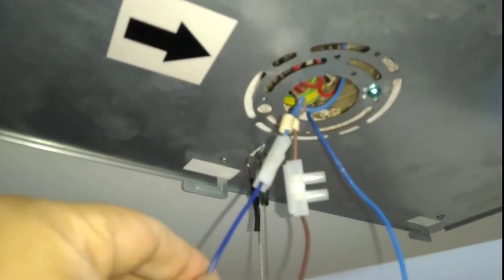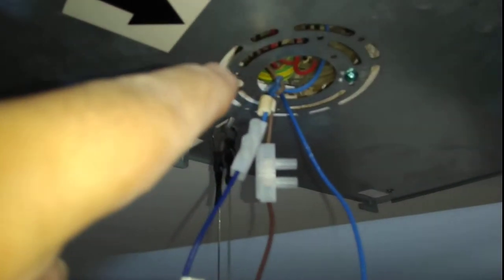And this is the wire coming from the old lighting. This brown one, as indicated on the back of this, is live, basically the mains, and this is neutral, which is N. If you put a test lamp, it shows red, which means live. You shouldn't touch it, basically. And this is the ground, which I didn't have in the same color, but I got the ground from here. You can see the green at the back, but I didn't have that color, so I used this one, which is the same thing, only the color is different.